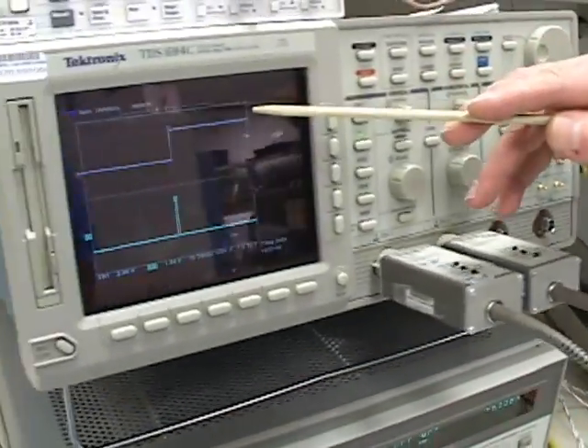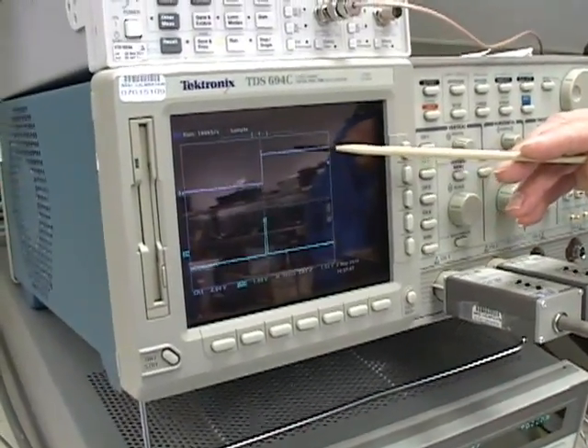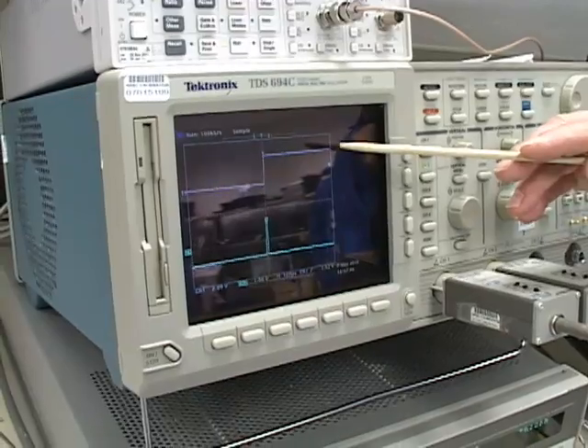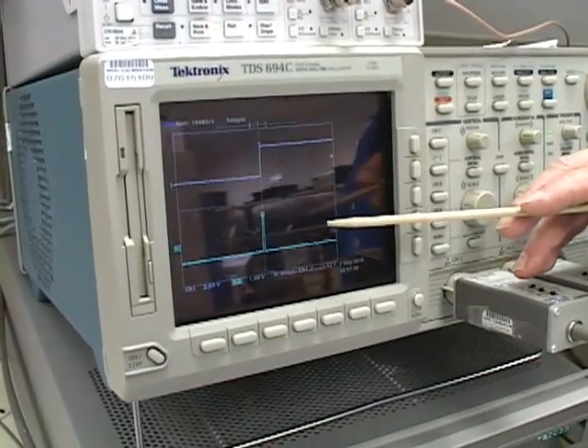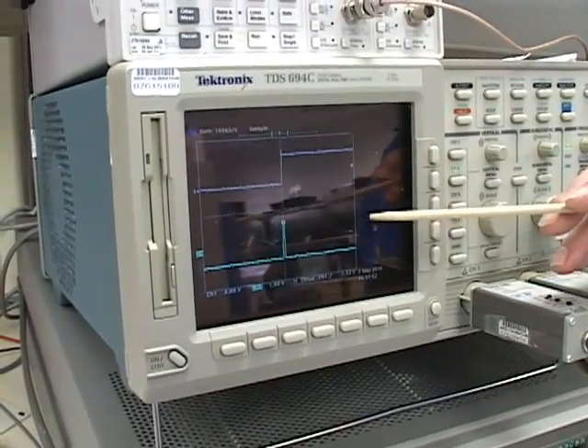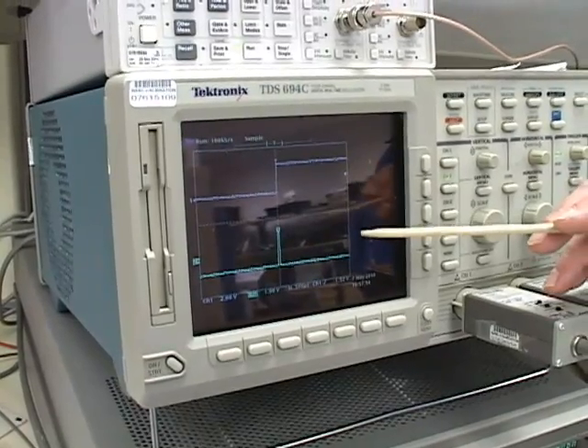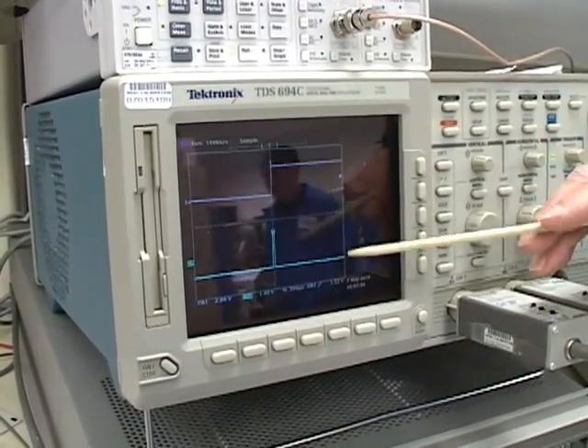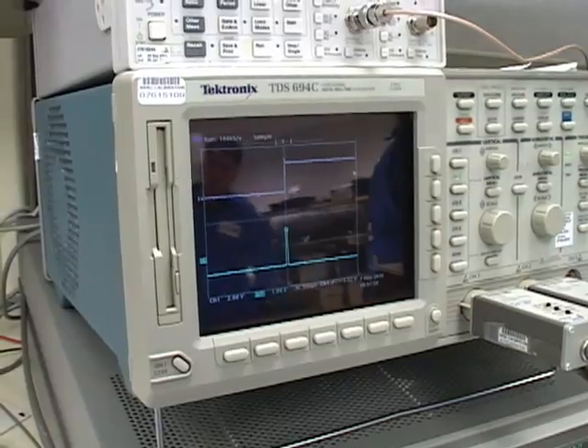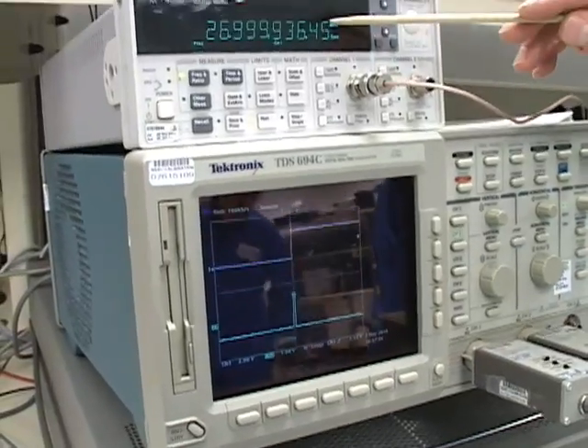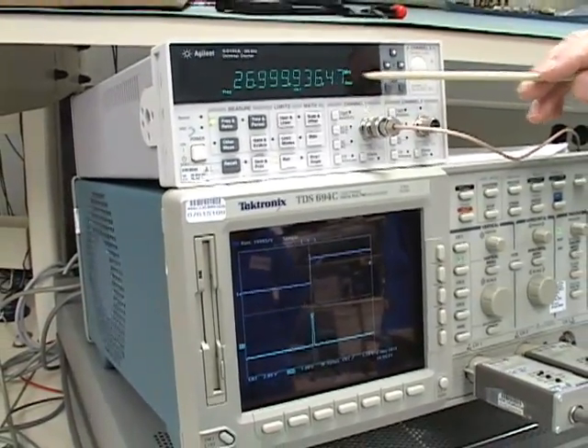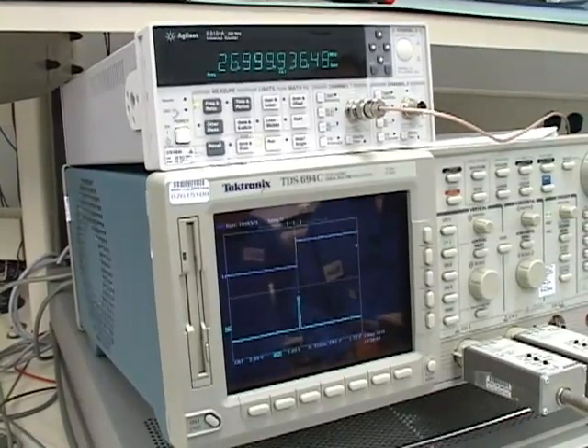What I'm showing on the scope here is my F input that's coming from my sync generator and then the lower trace is the top of frame signal for the first output. I have them set up now so that they're lined up and you can see the clock frequency that's being generated is the 27 megahertz clock frequency.